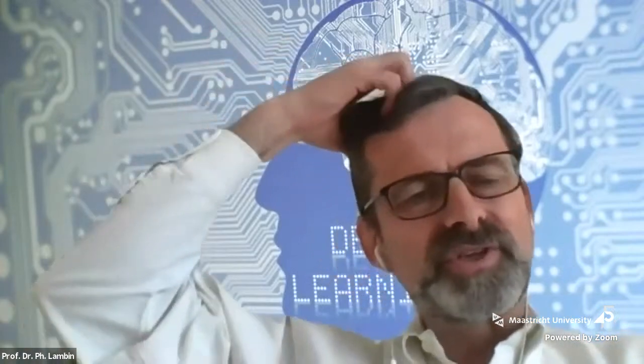Would you have to have several references, or would you have to generate a reference for each patient? How would you deal with a multiracial population, if you think that pigmentation has a significant impact? So the recommendation from the company is that ideally we should do the calibration for each race.